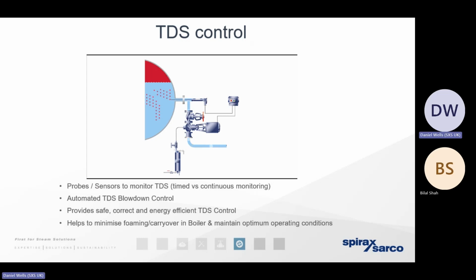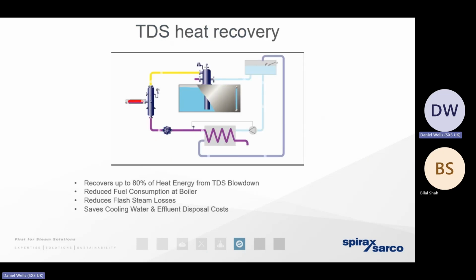Now, unlike the bottom blowdown that's got that grit and that particulate in it, there is an opportunity for a little bit of basic heat recovery with a TDS system, because we're not going to have any aggressive particulates that could result in erosion. We can take that heat energy away and potentially add it back to the hot well. So if we've calculated our client's cost of steam, cost of gas, we can guarantee what that payback is likely to look like.